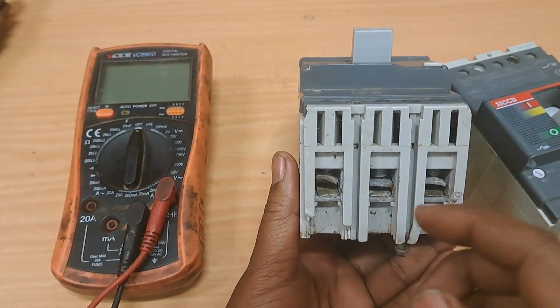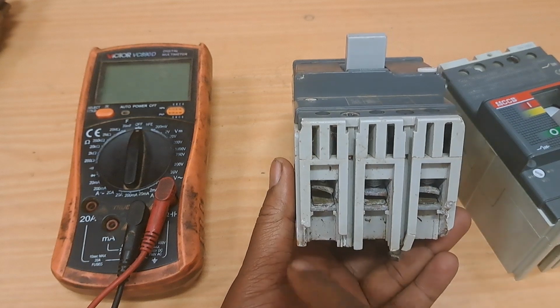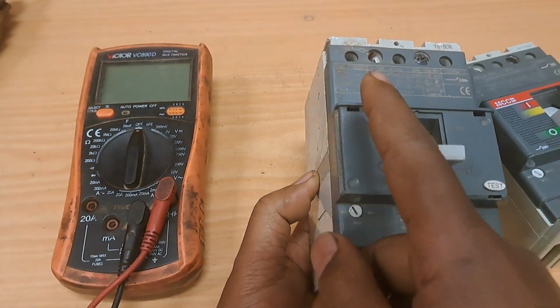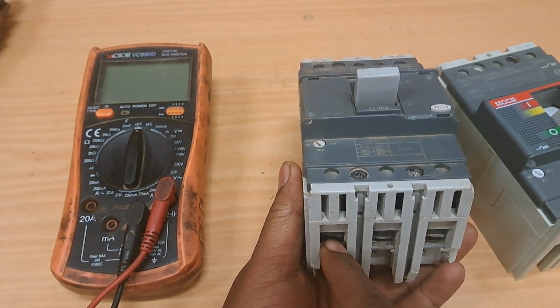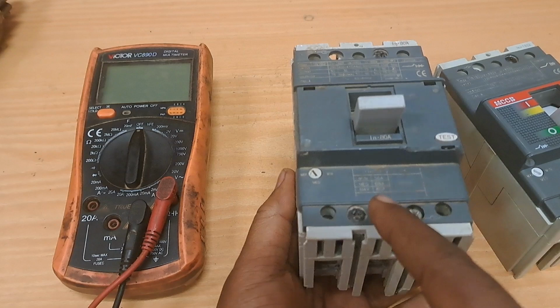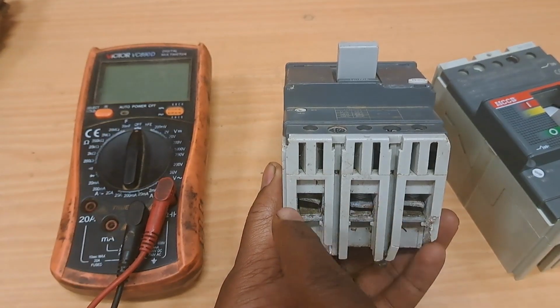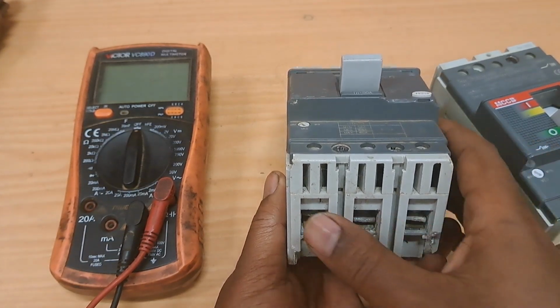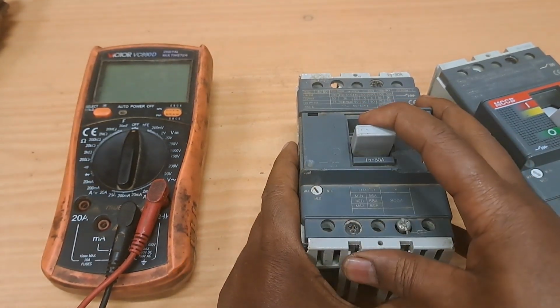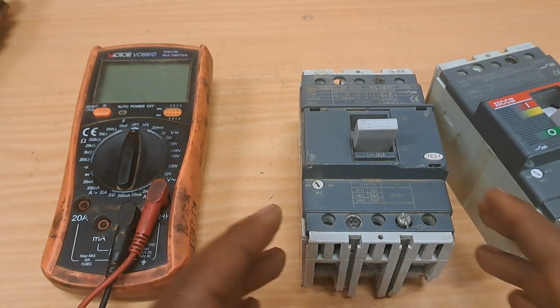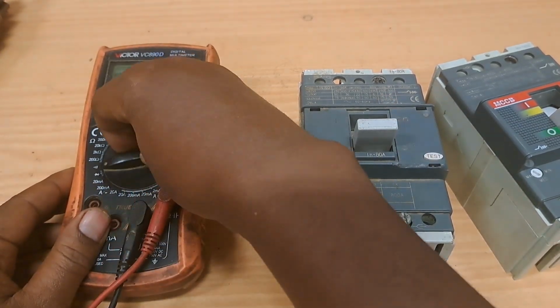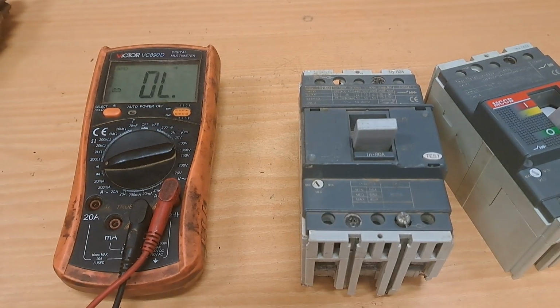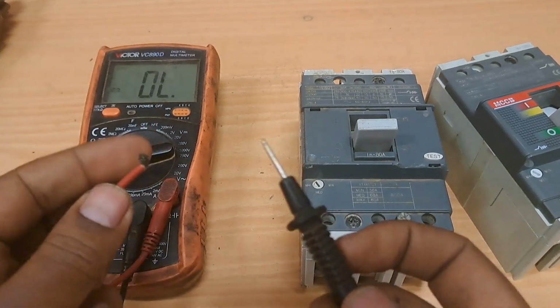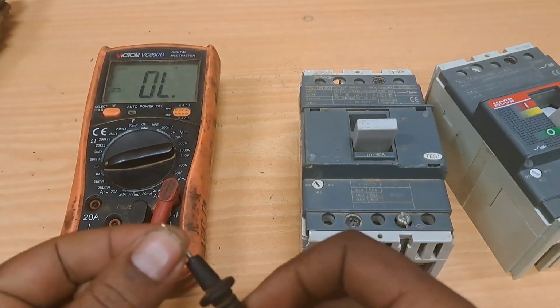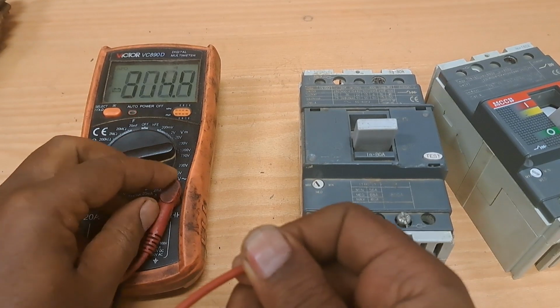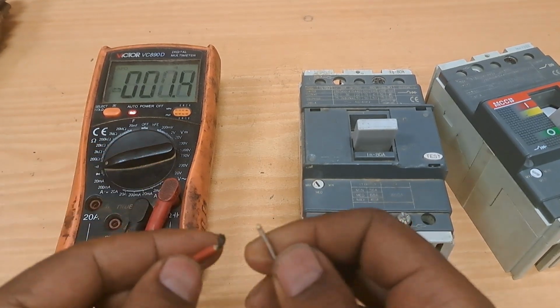For electrical continuity, we are going to measure basically two things. One, there has to be continuity between the terminals when turned on, and there should not be a short circuit across these terminals. Let's go ahead and do that. When turned to the off position, there should be no continuity. Let's place the multimeter on the beeping test so that you can use an audible test. You can also put it on resistance, lowest resistance value, and measure resistance. For this, let's place it on continuity and see.